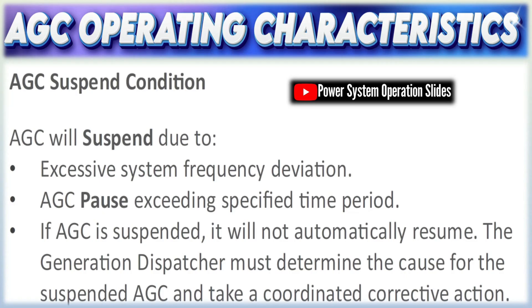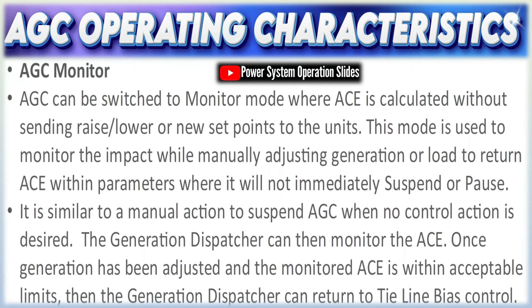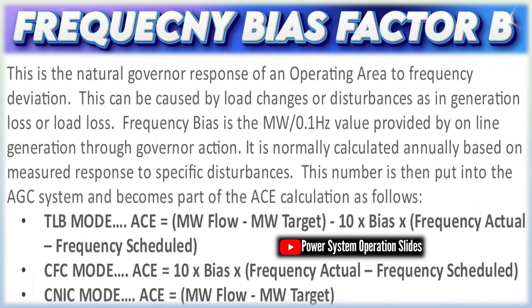The frequency bias factor plays a pivotal role in AGC by linking frequency deviations to required changes in power. Essentially, it quantifies how much extra power should be dispatched for every unit hertz of frequency deviation. For example, if the grid frequency drops below nominal, a higher bias factor ensures that the AGC quickly commands additional generation to arrest the frequency decline. Conversely, if frequency rises, it prompts a reduction in generation. The closer this bias factor is tuned to the actual frequency response characteristics of the control area, the more effectively the AGC minimizes deviations and enhances grid stability. Miscalculation in this parameter could lead to either sluggish or overly aggressive responses, potentially threatening system reliability.